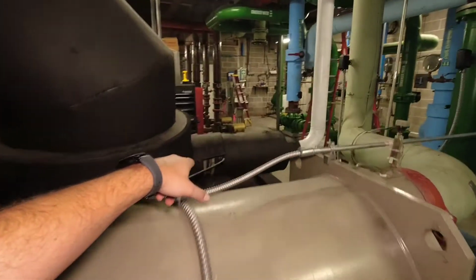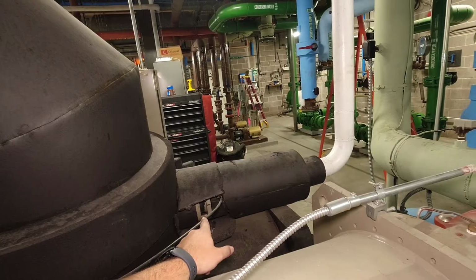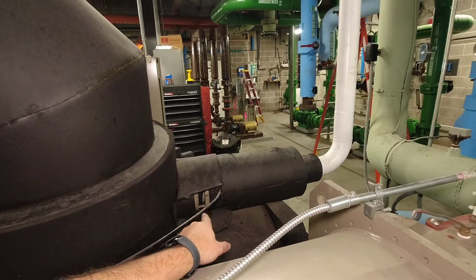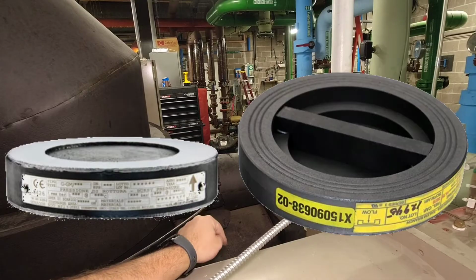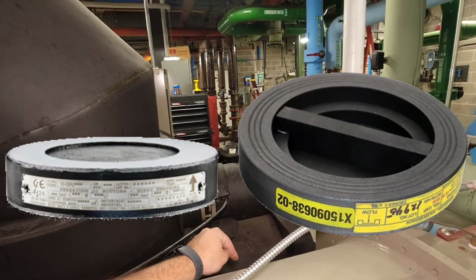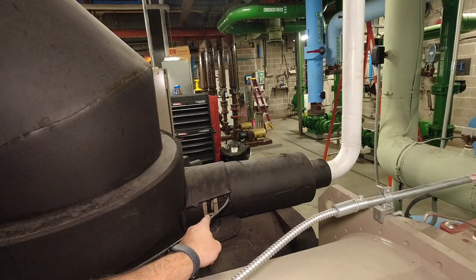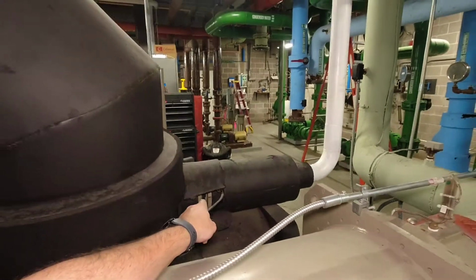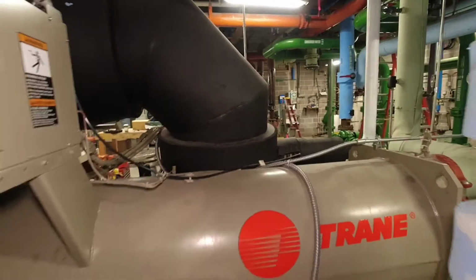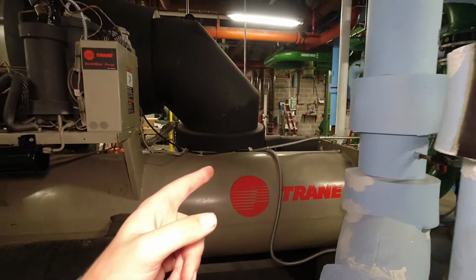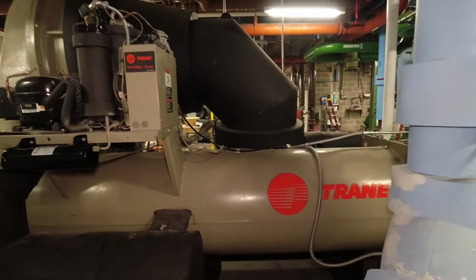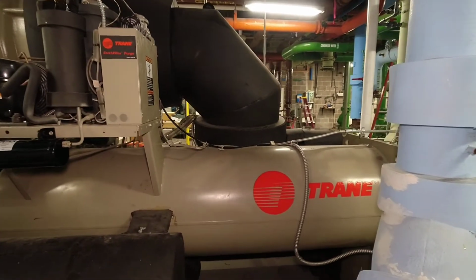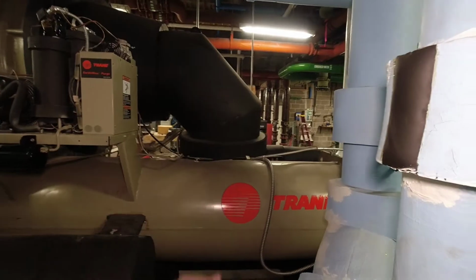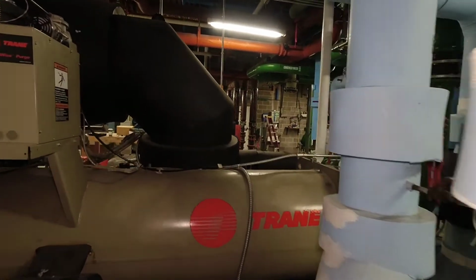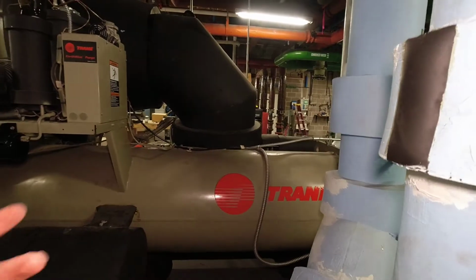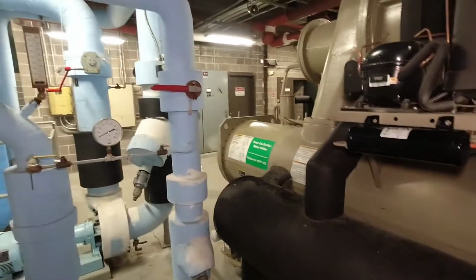This here, sticking out of the suction elbow, this is your burst plate. Most of those are set on this, so this is a 123 machine. All your low pressure machines will have a burst plate in them, and they're usually set for 15 psi. So when that evaporator suction gets up to 15 psi, which is really easy to do when you're pressure testing if you're not paying attention, you'll overpressurize it and burst that plate, and you're talking anywhere from $500 to $1,000 to fix that, depending on which manufacturer you're working on.